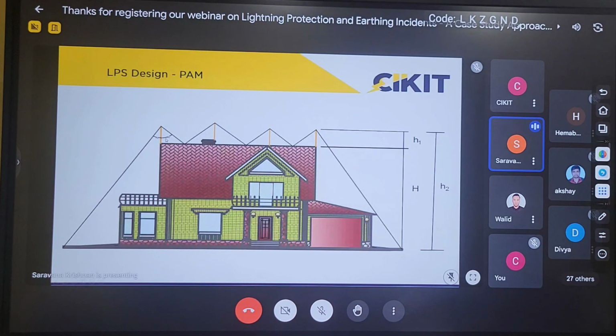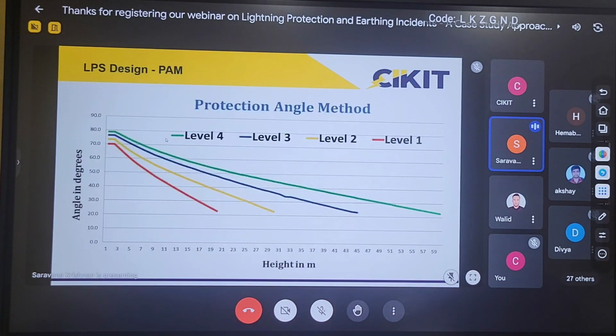If the height of the air terminal is 2 meters above this terrace, then I have to consider the angle for 2 meter height. And if I consider the height on the left side, then I have to consider the height of the building also. So, if the building height is 10 meter, then the overall height will be around 12 meter. This is the graph provided with the standard for performing these calculations.